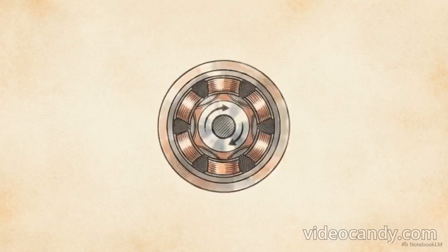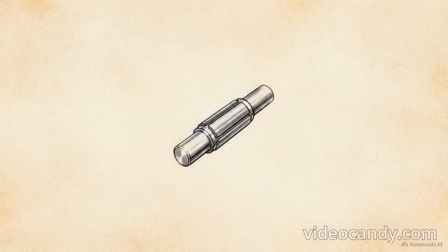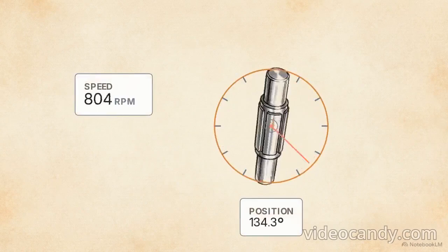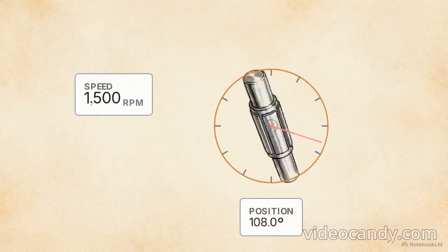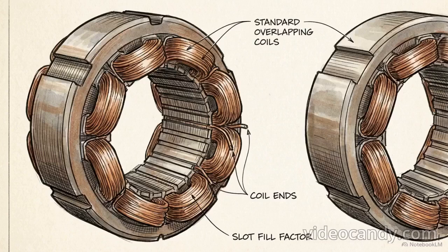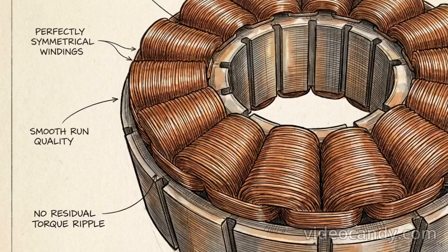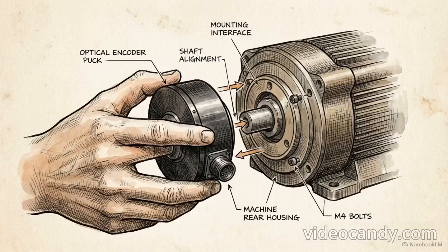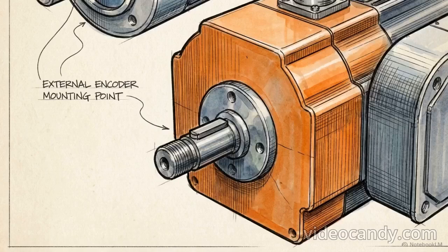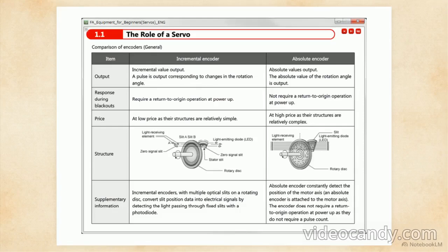While the mechanical housing protects the motor, the feedback loop acts as the critical sensory mechanism that dictates its ultimate precision. At baseline, all MAC motors feature an integrated tacho feedback system. This handles continuous speed evaluation and basic rotor position recognition. Standard tacho feedback covers most applications, but precision lathes require a high smooth run quality variant. This specialized tacho is wound specifically to minimize residual torque ripple during rotation. Achieving exact positioning control requires a structural modification. The motor must be expanded with an accessible second shaft end, providing a mounting point for an external encoder.